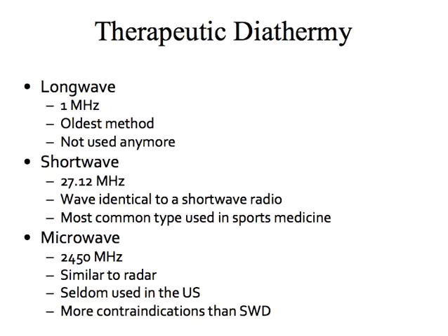There are three general types of therapeutic diathermy units. Longwave ran on a 1 megahertz frequency — it's the oldest method and is not utilized anymore. Shortwave is the most commonly used in sports medicine; the waves are identical to shortwave radio, most often at 27.12 megahertz. It can be further divided into continuous, which is not used anymore because it would get too hot, and pulsed, which is the most often used type.